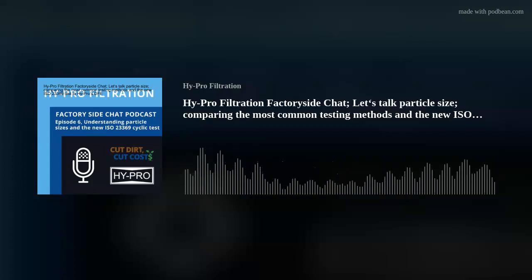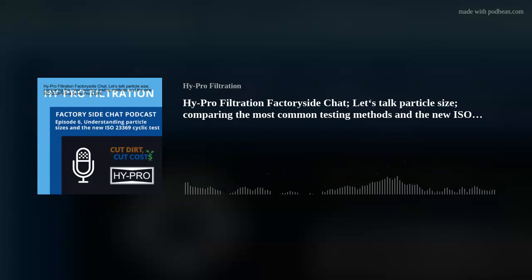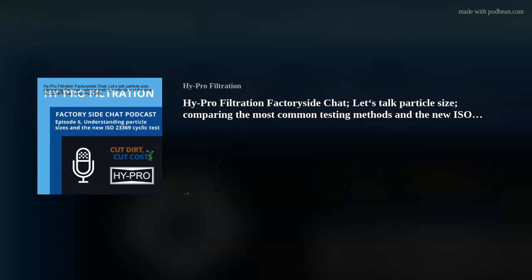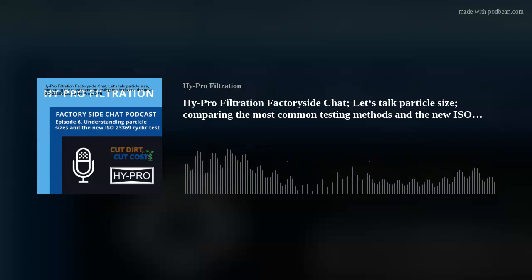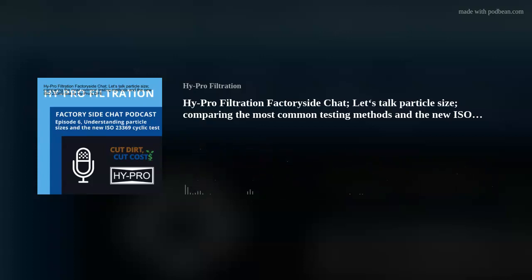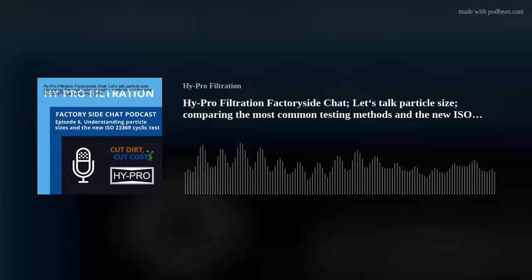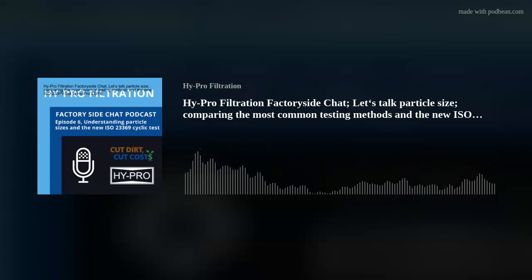Yeah. So the testing we do is called DFE testing, meaning dynamic filter efficiency. And like you mentioned, about 25 years ago, we realized and understood that the 16889 test was not mimicking real world conditions. So we wanted to test our filters as close to a real world environment as we possibly could in a lab setting and see how they performed versus a steady flow test.